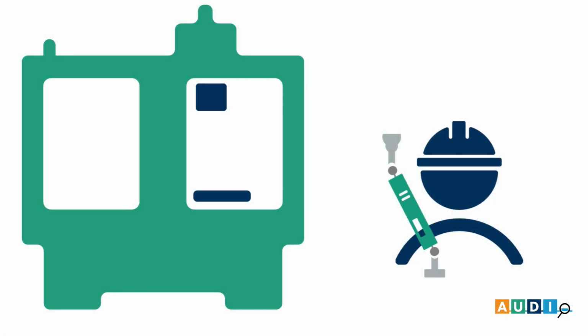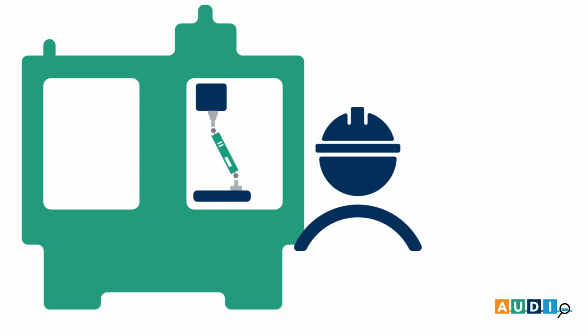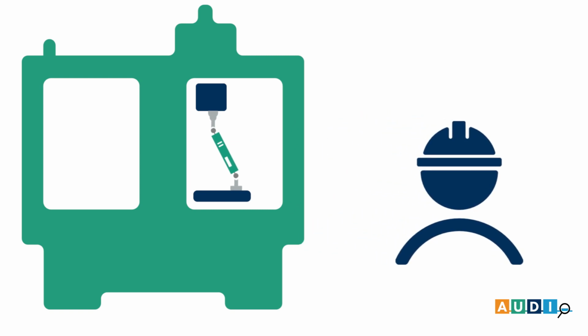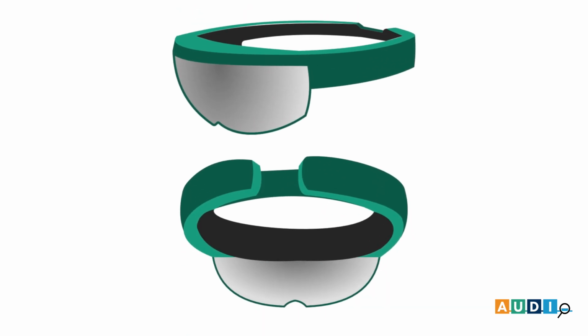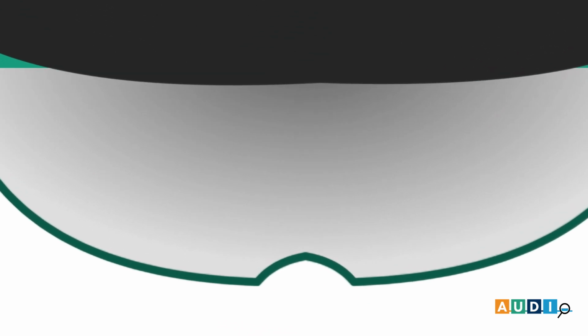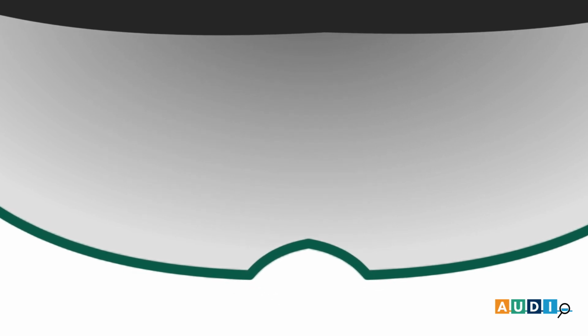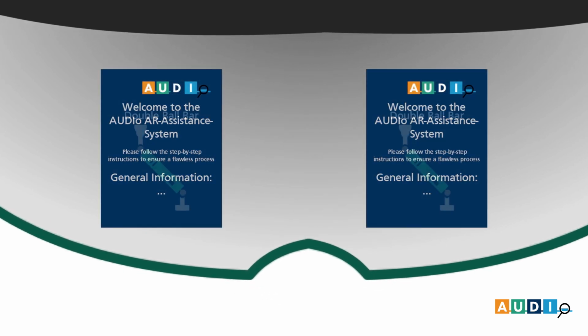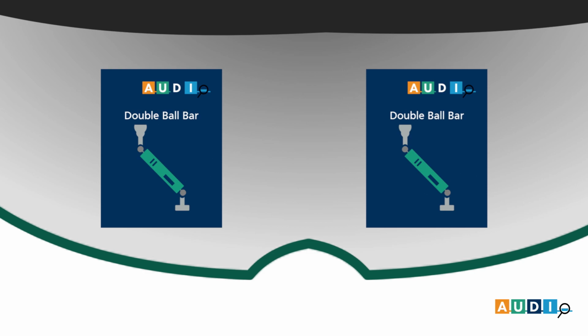This simplification and use of the double ball bar compared to the single point measurement allows a machine operator to perform the measurement himself without additional training, using reduced instructions. In order to be able to transmit these instructions to the machine operator as comfortably and reliably as possible, an assistance system was developed in augmented reality. This guides the operator through every single step of the service process, from setting up the double ball bar to sending the data to the service provider.